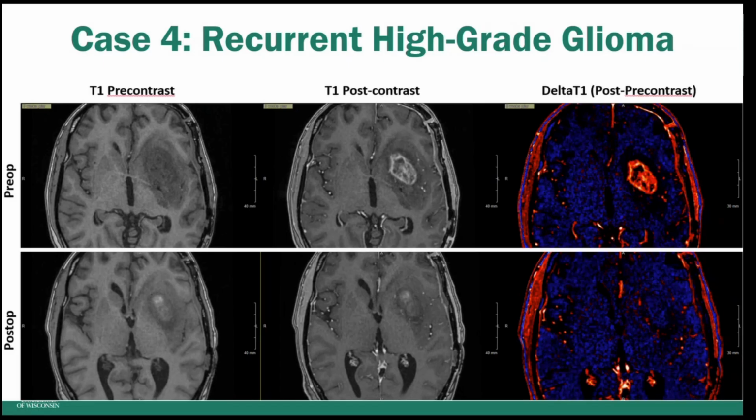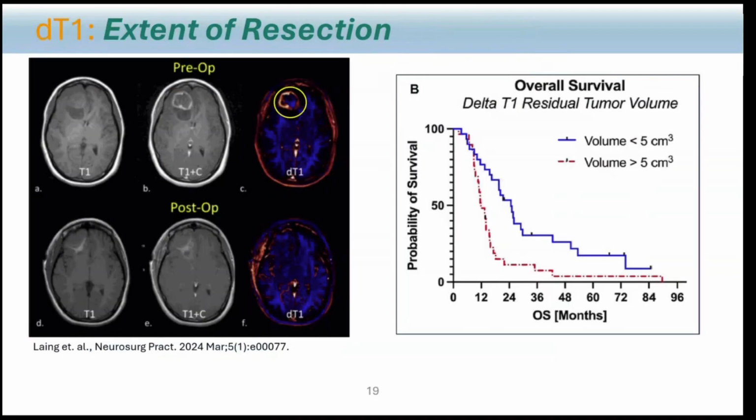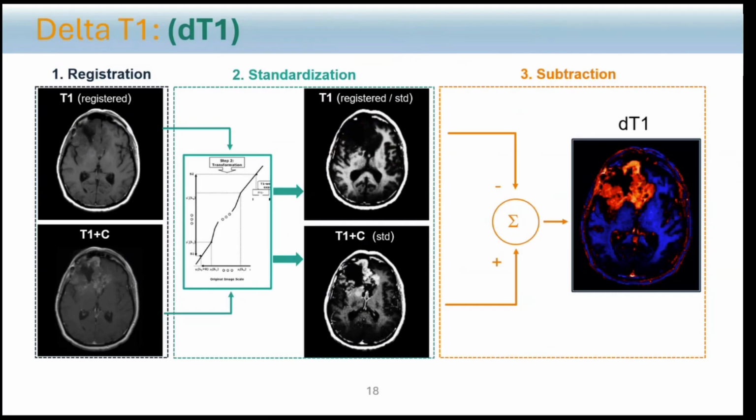The delta T1 maps are fully quantitative across time and scanners and field strengths. So there's an intrinsic numerically characteristic value with that. So it's not a relative or subjective output map. It's truly quantitative. So are those just the difference in terms of image intensity and pre and post contrast? Yeah, that's the details of the standardization technology. It's a calibration to a fixed and consistent scale that's done once for all time, and it's built into our software that makes the output truly quantitative.